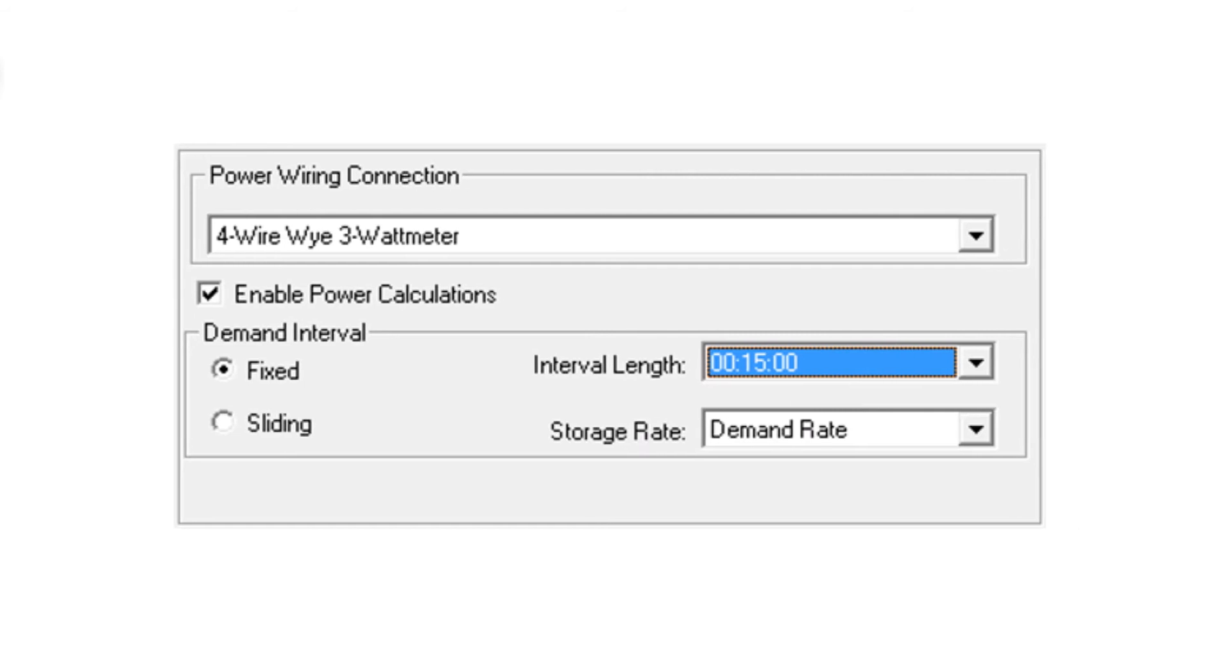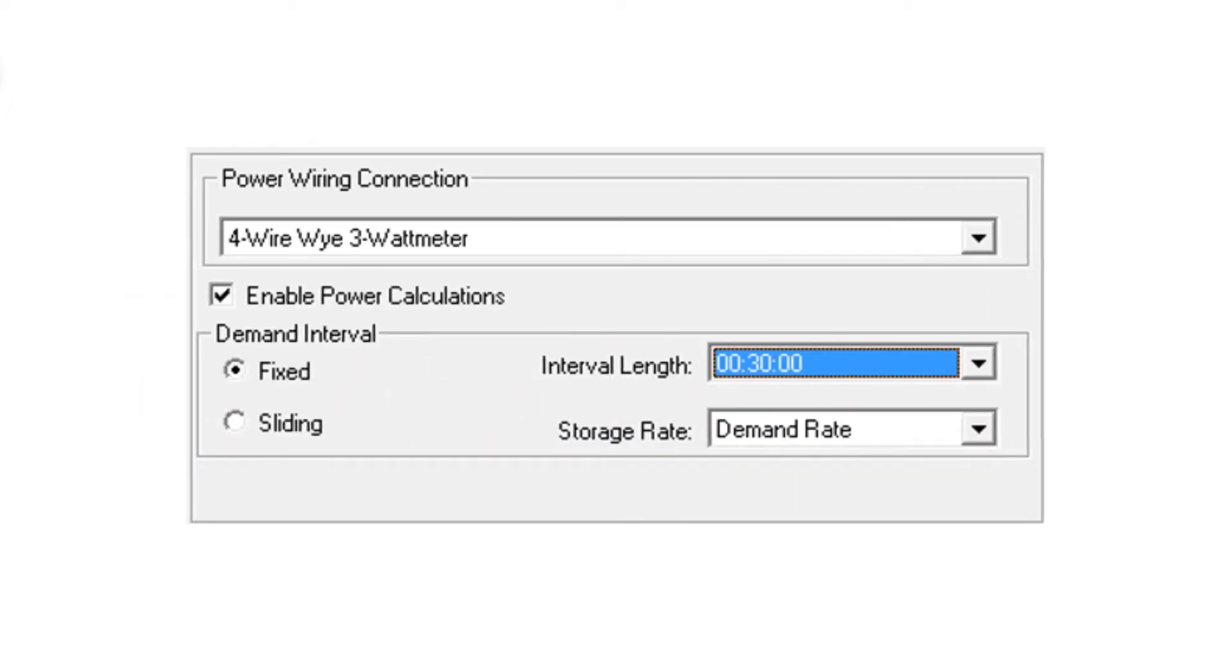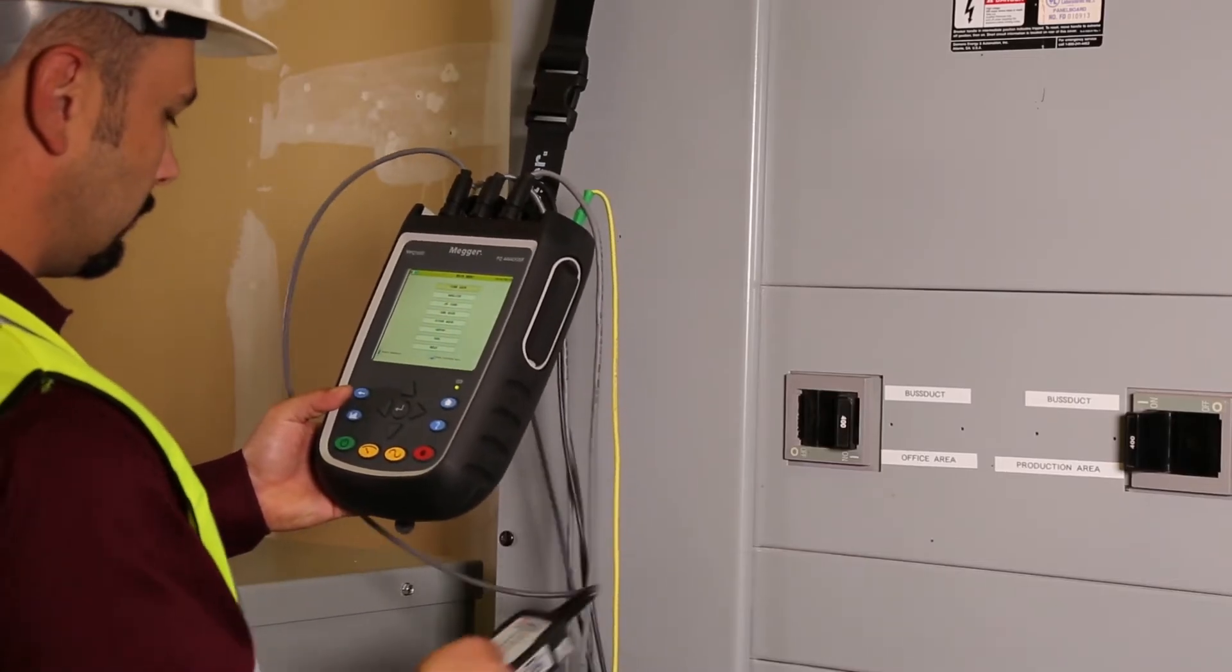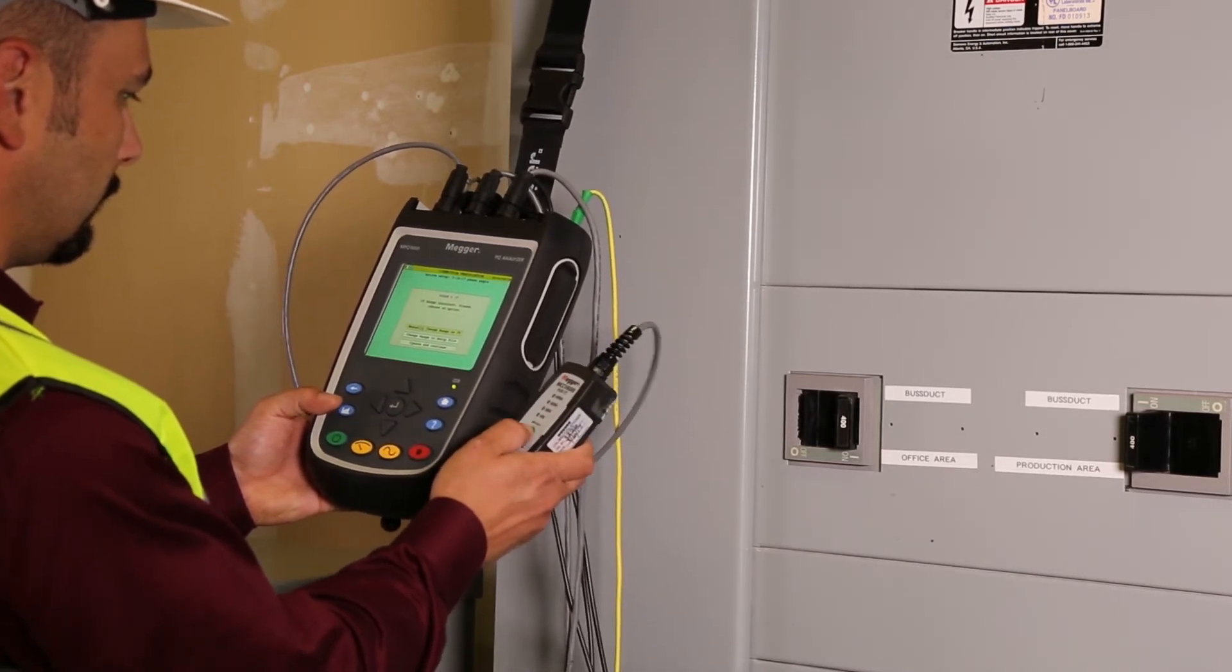This interval can be based on a 15-minute fixed interval, but not always. For example, the interval can be 30 minutes, or they can be fixed or sliding intervals. Most meters don't allow you the flexibility to match your revenue meter's aggregation rate. MPQ does allow this. Without this, you don't get the proper answer and cannot perform an adequate energy audit.